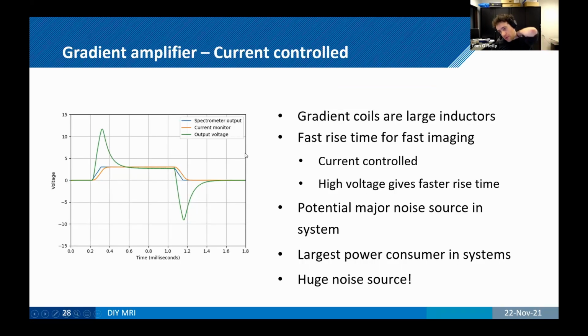So your gradient amplifier basically is used to put current through your gradients, obviously. And your gradient coils are large inductors. So if you want to have a fast rise time on your gradients, you don't want to integrate a constant voltage over time to get your current. So typically gradient amplifiers are current controlled, which means that they'll overshoot your output voltage to lift the current up to its desired strength much more quickly. This is one of the power limiting things on your gradient coils. Typically the voltages aren't very high because your resistances aren't very high, but they are high when you're switching your gradients. A higher voltage will give a faster rise time.